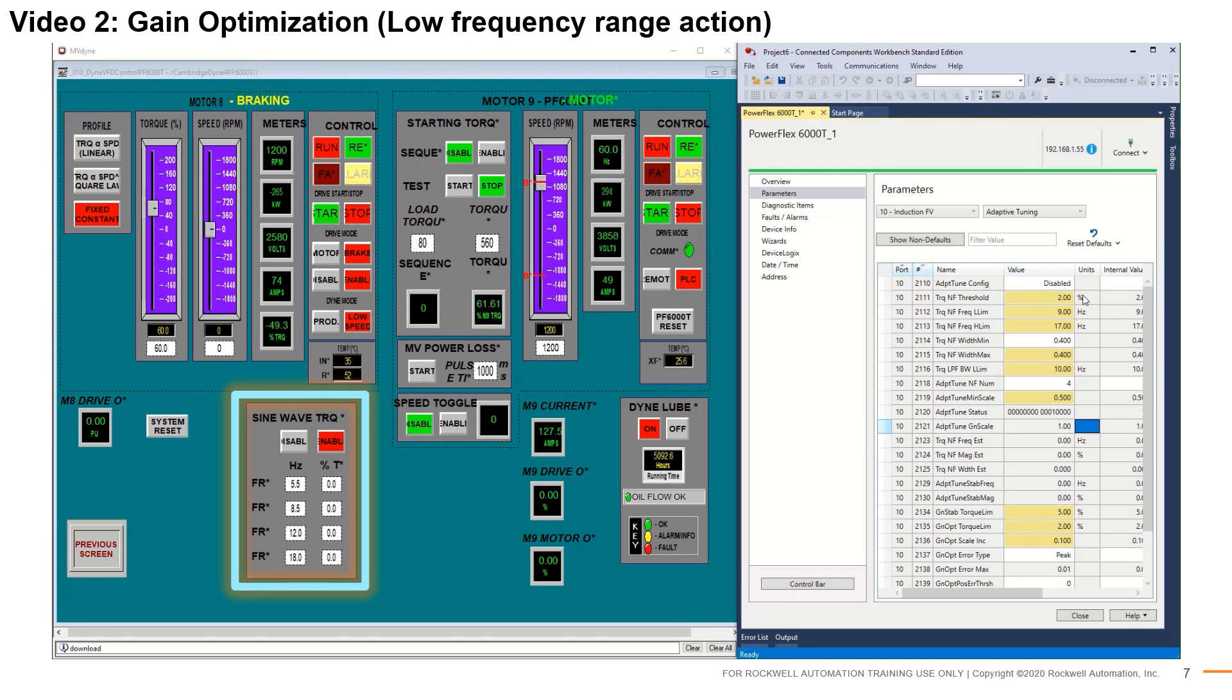Let us move on to adaptive tuning's action in the low frequency range. We will be seeing how the regulator gain scalar changes in response to the presence of low frequency harmonic content. For this demonstration, only one frequency will be injected. Recall that the low frequency limit is set by parameter number 2112. It is currently set to 9 Hz. Adaptive tuning mode shall be set to gain optimization.